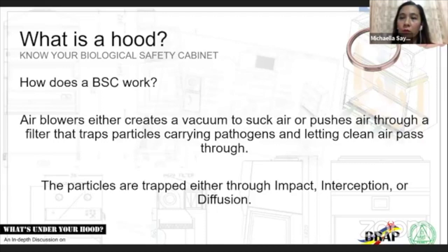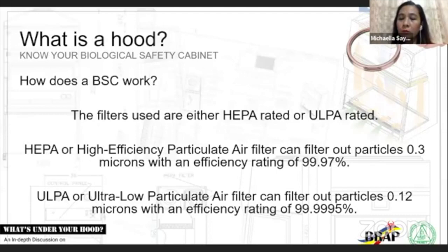Okay, now the particles are being trapped either through impaction, interception, or diffusion. We'll go into this. But first, we need to know what our HEPA filters are. So the filters are either HEPA-rated or ULPA-rated. Now, if you say HEPA, it means high-efficiency particulate air filter. So if you say HEPA, you must include the word filter at the end. It can filter out particles of 0.3 microns with an efficiency rating of 99.97%.